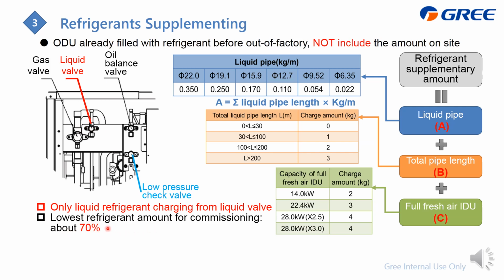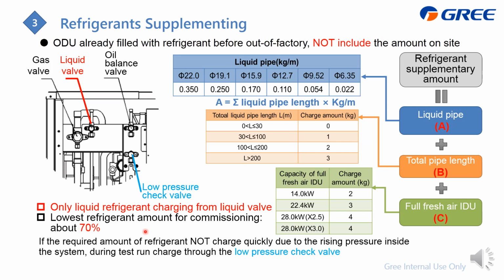If during the charging you find that as you charge more refrigerant the pressure also increases, right? At that time you find that the refrigerant is not that easy to charge in, and you can also charge during the test run, from the low pressure check valve, either in cooling mode or heating mode, it is okay.